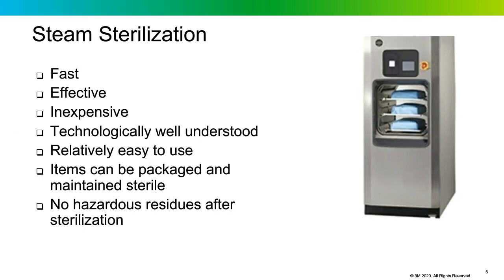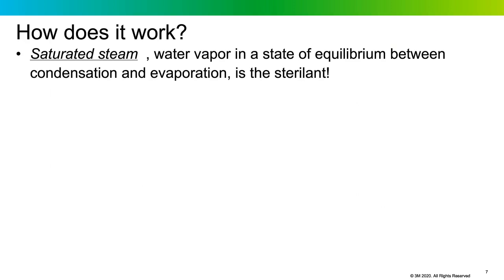Steam sterilization is prevalent because it is reliable, consistent, economical, and an effective method of sterilizing reusable instruments. The technology is well understood, items can be packaged to maintain sterility until the time of use, and there are no chemical residues, making it safe for both staff and patients. Saturated steam — water vapor in a state of equilibrium between condensation and evaporation — is our sterilant.